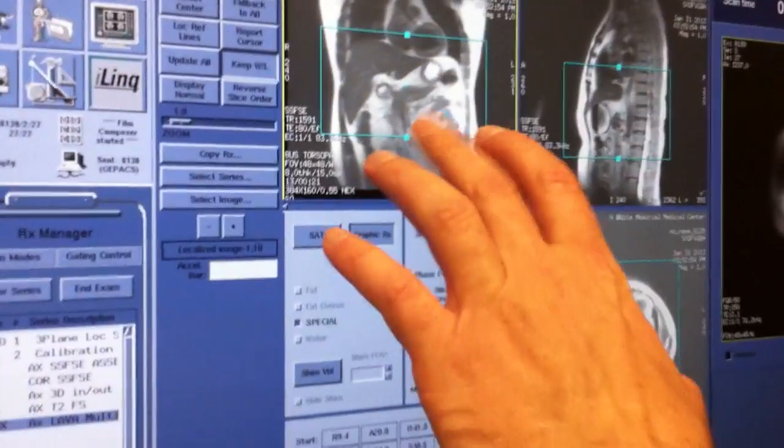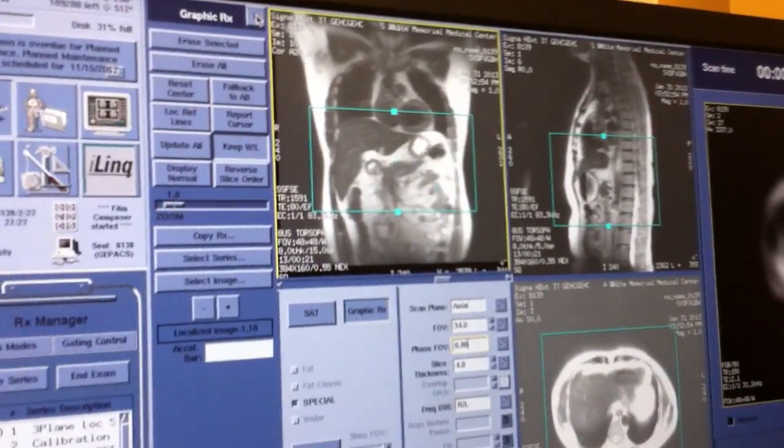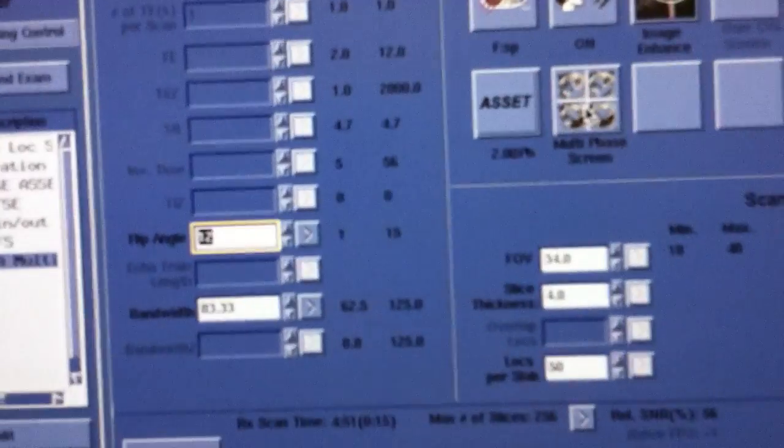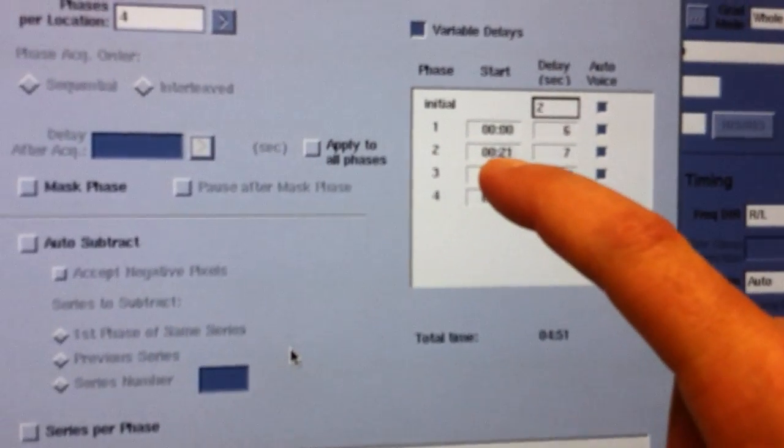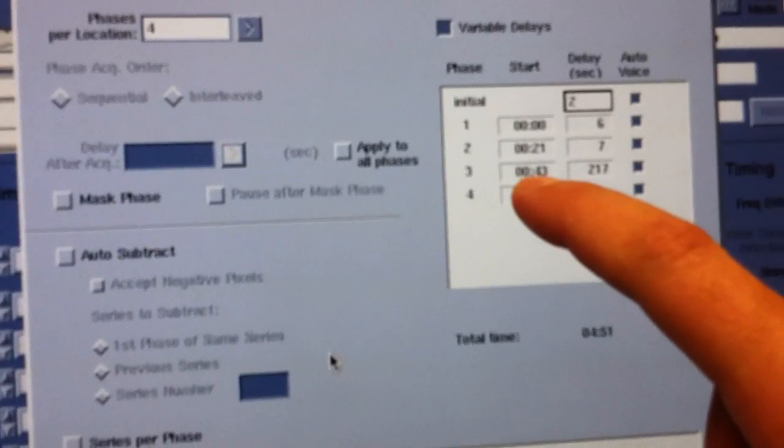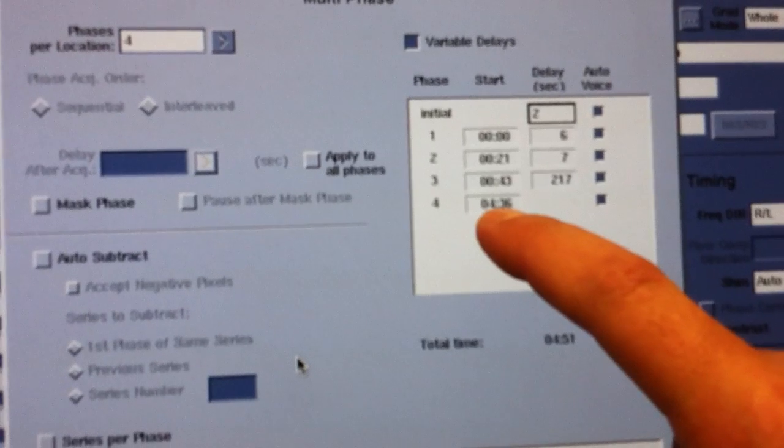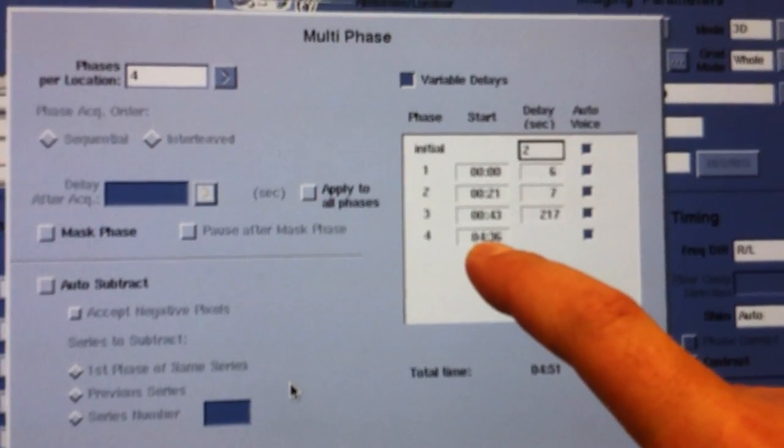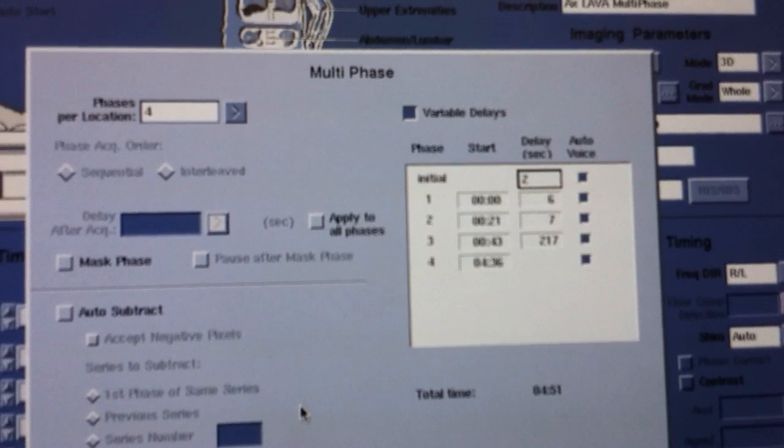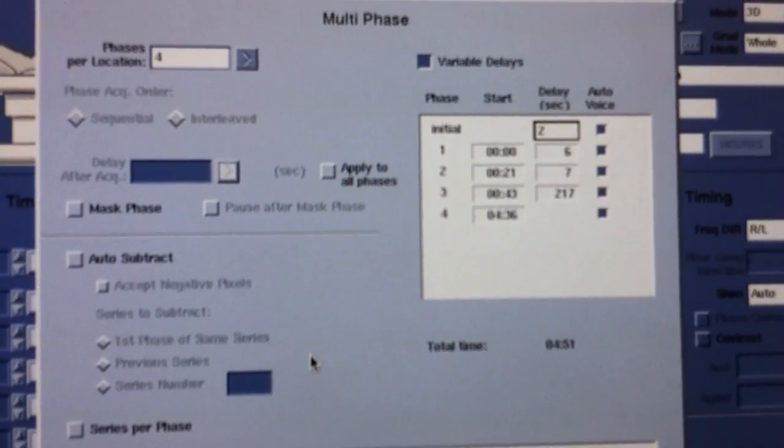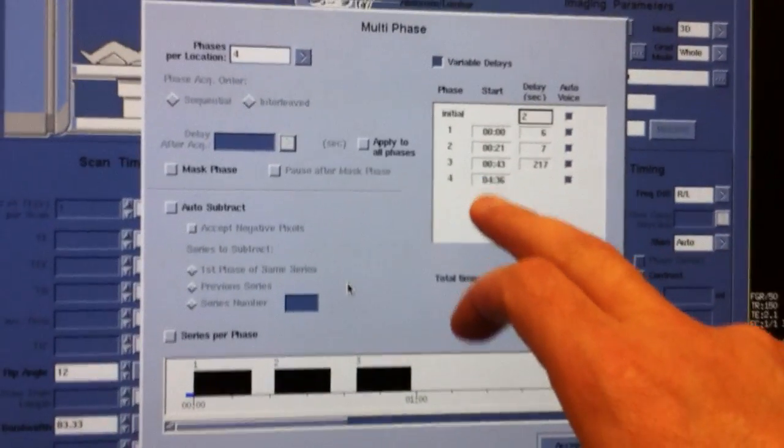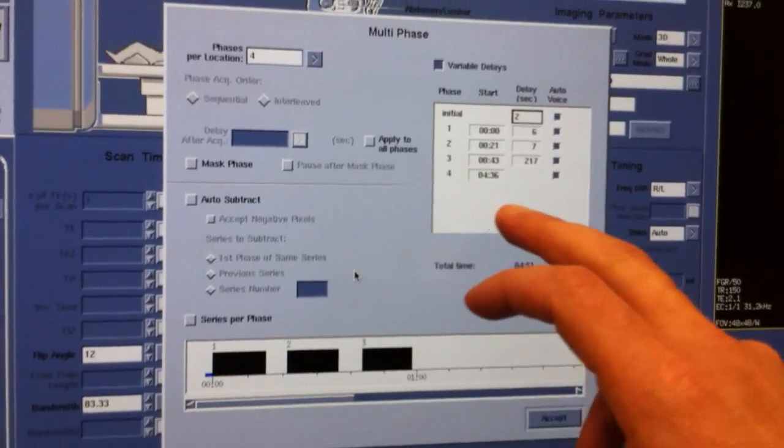So, now we're in our lava multi-phase liver. We're going to close our graphics. Now, in this case, we have a multi-phase screen here. If you need to adjust your multi-phase or you need to fix it per the doctor's protocol, this is what you would click. Now, in this particular, here at this site, we do four phases. We do a zero phase. We do a 21-second phase. It's also known as the arterial phase. We do a 43-second phase, which is like the venous phase. And then we do a five-minute phase four. It's about five minutes. In this case, 436. And it lets all the contrast wash out of the liver so we can see if any lesions are holding on to the contrast. So, this is how we do ours here. Some places do six phases. Some places only do three phases. We do four here.